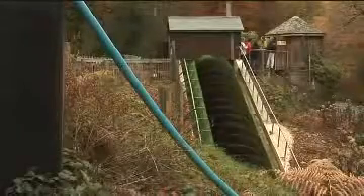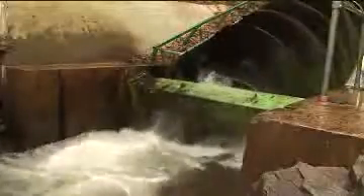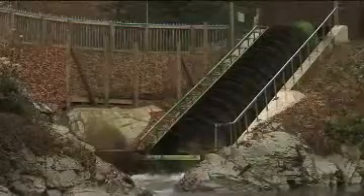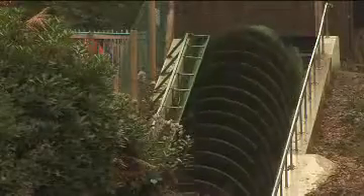The hydrodynamic screw produces a maximum of 48 kilowatts. It is dependent upon the water in the river. We have been running through the summer at pretty near full capacity at 45–48 kilowatts. During the dry spell in September and October it did drop down to 35 kilowatts, purely because of the limited volume of water we could take out of the river and down the leet. The power output is more than I actually budgeted for or envisaged in the planning stages, and I'm delighted at how well the whole scheme has come together. There is enough power to supply the main house, Home Park House, which is used as a wedding venue and conference centre, along with the associated buildings of a café bar and two bungalows. And any surplus we do export to the grid.